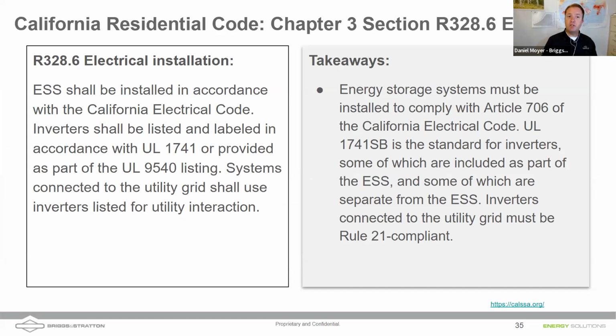Make sure you still follow your California electrical code or your NEC, whatever you're enforcing in your state. We want to make sure the inverters we're pairing with our batteries have the UL 1741 SB listing so they're able to be a grid interactive inverter.